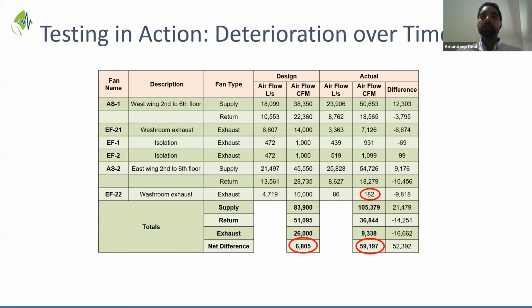And the exhaust, one of the exhaust fans, EF22, was designed as 10,000 CFM, and is actually running backwards. So when you add them together, the original design needed to be net positive around 6,800 CFM, but the system is actually running at 59,000 net CFM. So when you ask the facility, they just say that they had tons of pressurization issues with this building, and what happens with that is they can't close the door.